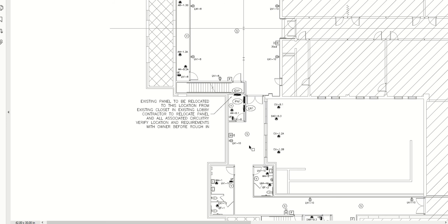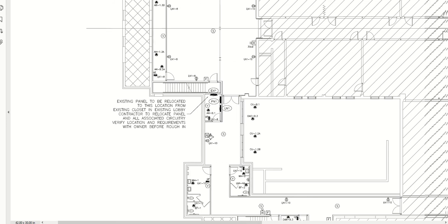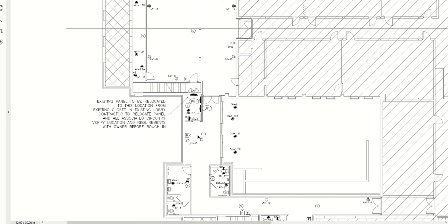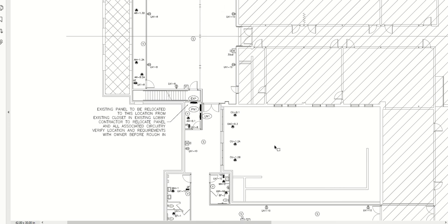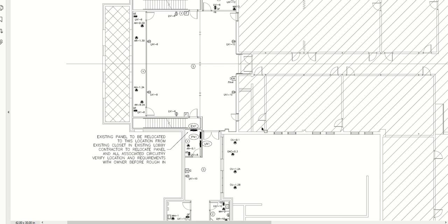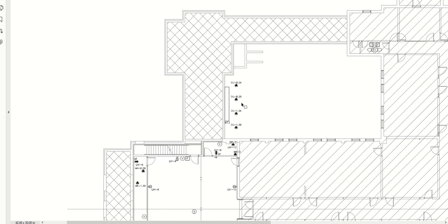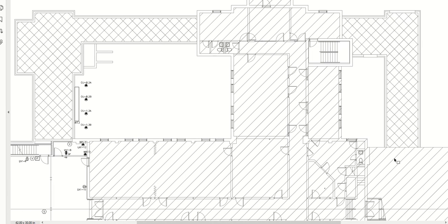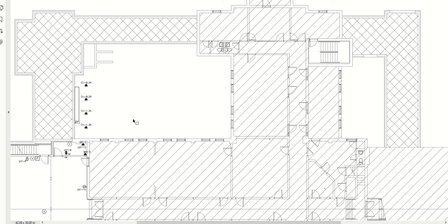We relocated this panel down to this closet and added two new panels for new loads. There's a little courtyard area here where the mechanical guys put condensing units. We're feeding these with a wire trough from an existing panel located back over here. Instead of setting another panel just for four loads or running four feeders all the way over, we ran one feeder to this wire trough and then tapped off using enclosed circuit breakers.